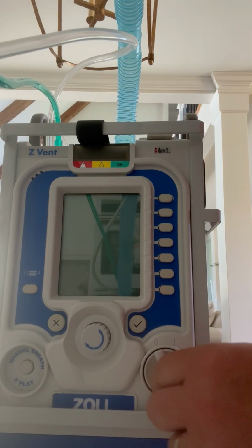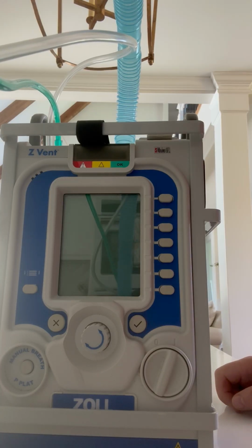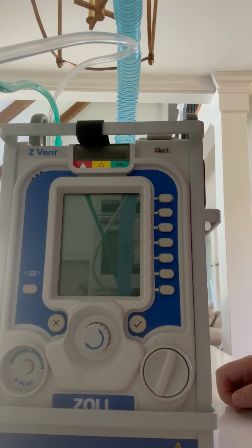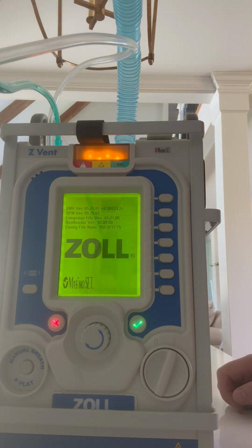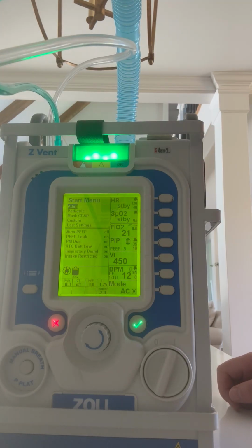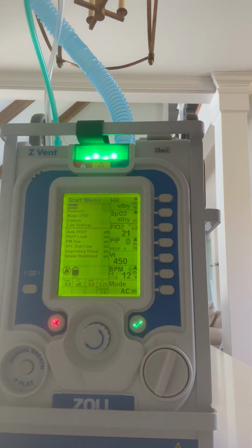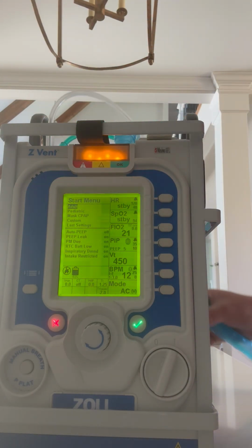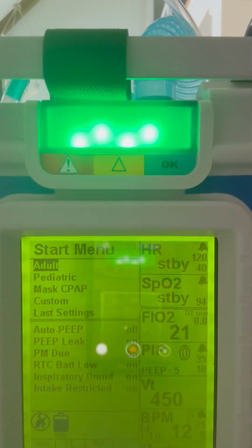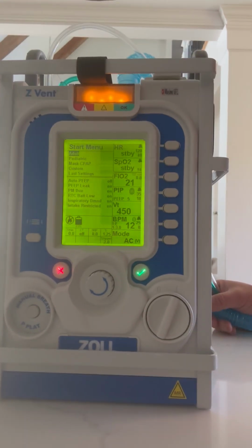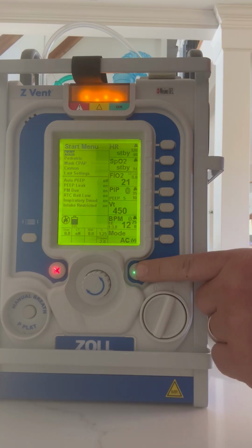On switch, every single time you turn the ventilator on, it does a self-check calibration, and it is ready to go. So you'll know immediately if there's anything wrong with the ventilator. Upon turning it on, there's a nice little menu screen. It tells you adult, pediatric, mask CPAP, or a custom or last used or last settings. The green check mark to choose your option.